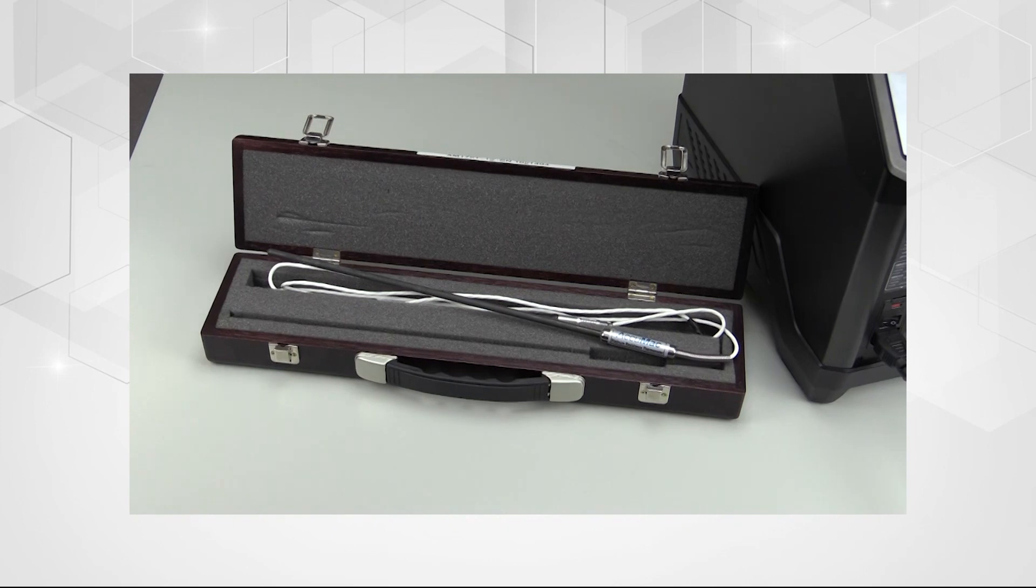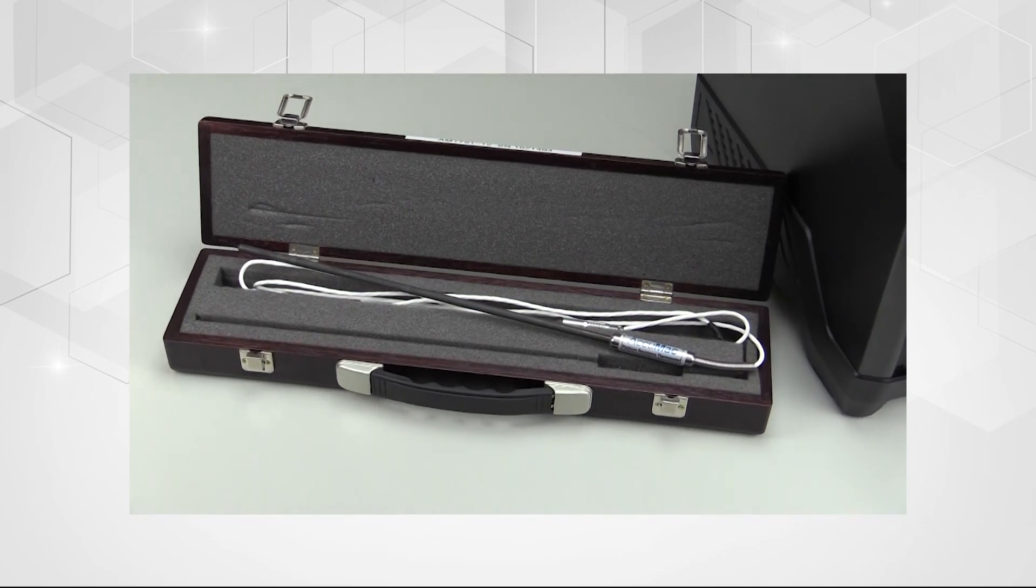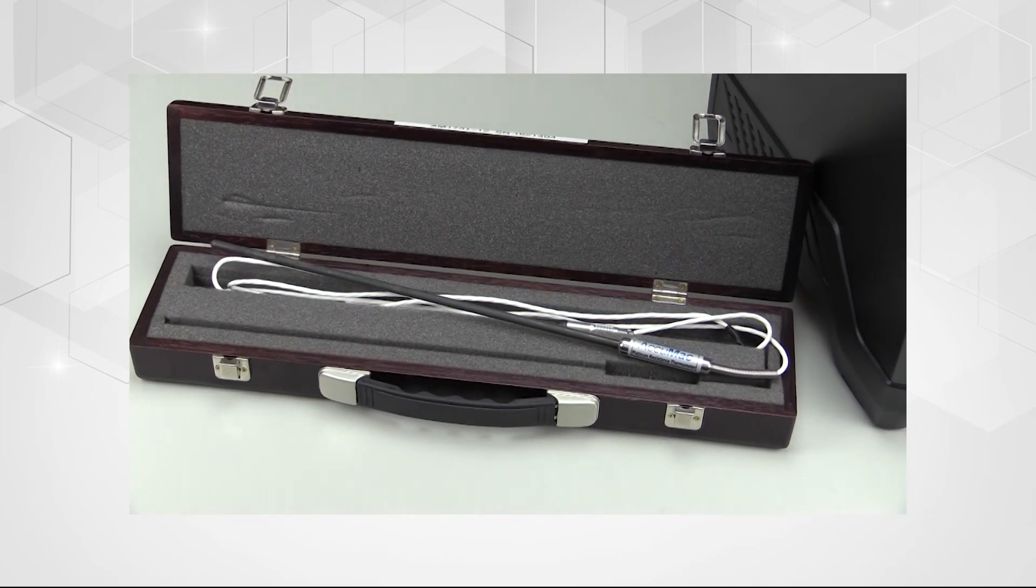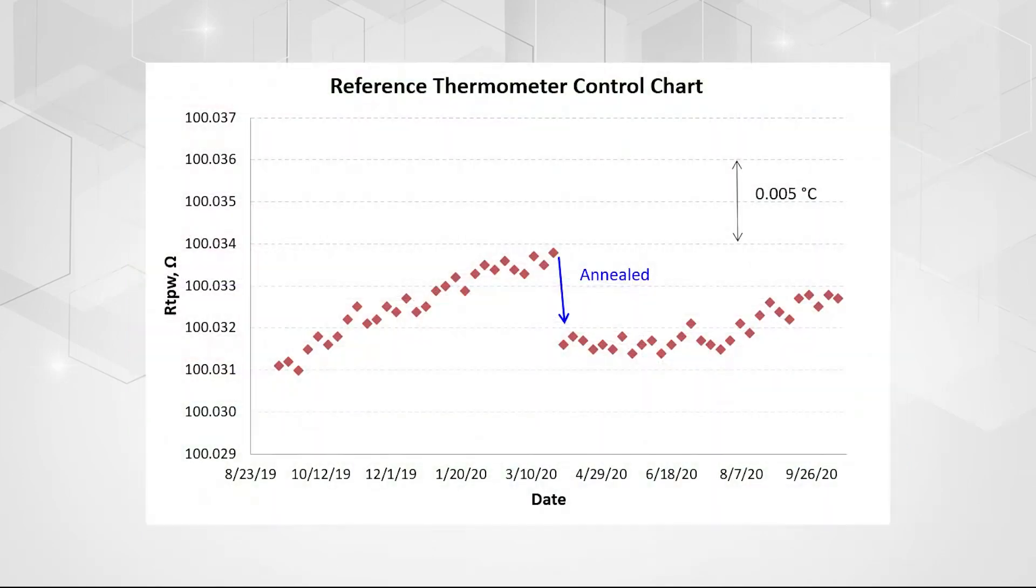During normal use and over time, platinum resistance thermometer probes build small amounts of stress and oxidation in the platinum wire. These subtle changes have an impact on the resistance values of the probe, which in turn impacts the measurements they take. By consistently measuring and logging the resistance of the probe with a TPW device, good control can be achieved.